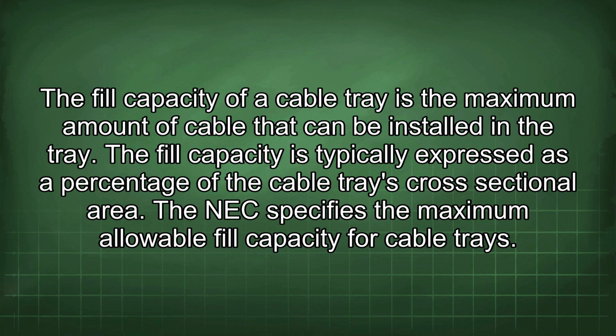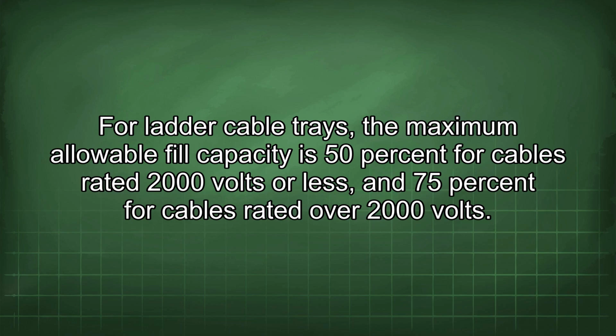The fill capacity of a cable tray is the maximum amount of cable that can be installed in the tray. The fill capacity is typically expressed as a percentage of the cable tray's cross-sectional area. The NEC specifies the maximum allowable fill capacity for cable trays. For ladder cable trays, the maximum allowable fill capacity is 50% for cables rated 2000 volts or less and 75% for cables rated over 2000 volts.